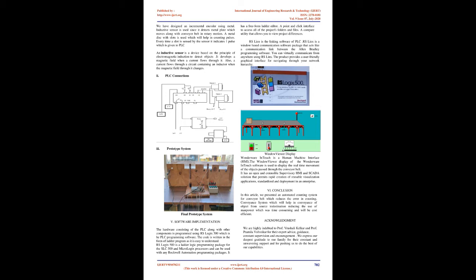An incremental rotary encoder provides great speed and distance feedback compared to other types of rotary encoder, and features fewer sensors, making it less expensive and having fewer possibilities of failure. As the disc rotates, the patterns interrupt the beam emitted onto the photodetector and generate a pulse signal output. An incremental encoder generates a pulse for every incremental step in its rotation. The 2 sensors of the incremental encoder allow it to determine the direction of the rotation, since the 2 sensors are 90 degrees out of phase in terms of the generated waveforms.